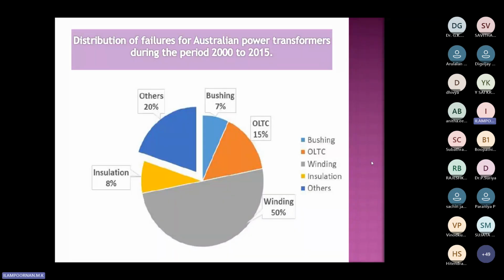As you can see here, 50% of the failure arises because of winding deformation or winding problems. Then insulation problem is 8%. There are other problems like loosening of nuts, bolts, structural changes, everything - if put together, it is 20%. Then because of bushing, the transformer may fail, that is around 7%. Then on-load tap changer, OLTC, that is one of the major causes for transformer failure. So from all these things, you can get an idea which part of the transformer causes major failure.